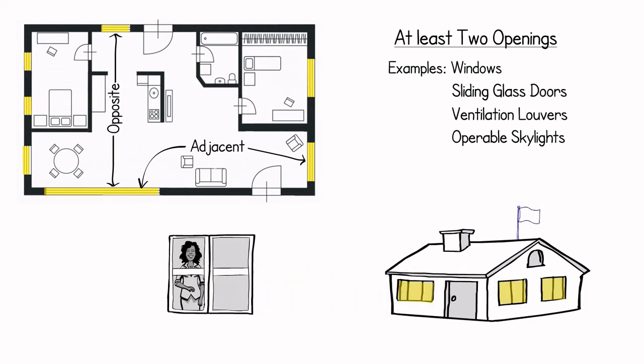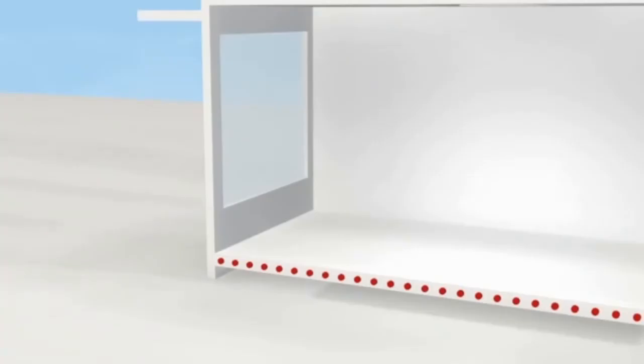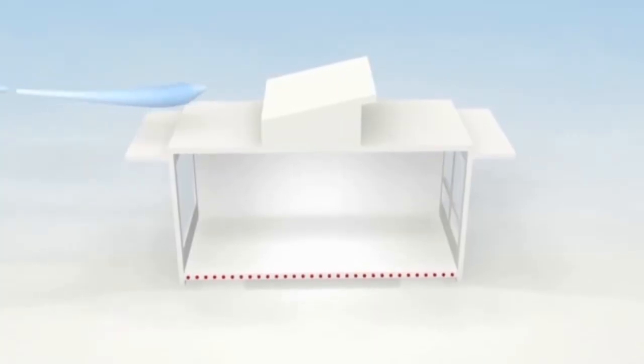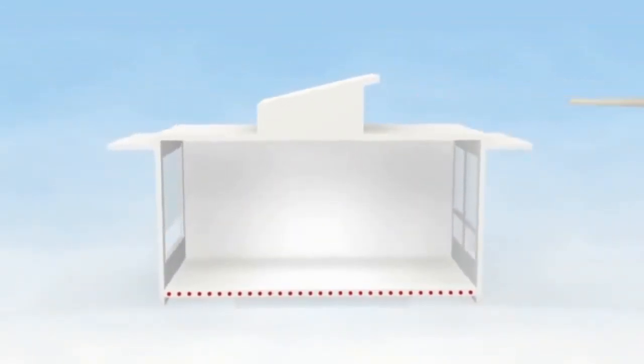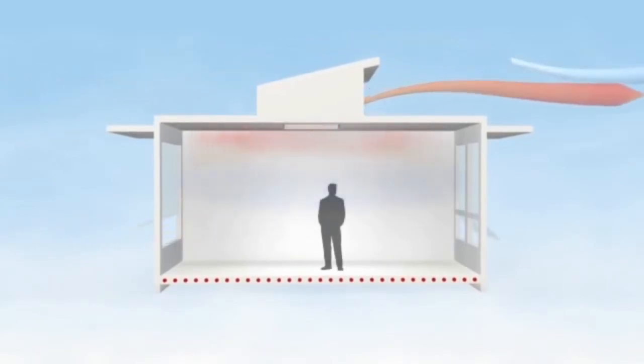The amount of heat to detach from a building, house, or infrastructure is directly affected by those areas. If the inlet and outlet areas are bigger, then more air can travel through, meaning more heat can be removed, and vice versa. However, discomfort will be created if inequality is observed — meaning the air coming in is higher than what is going out or vice versa. An equal amount of airflow volume going into a building as exiting the building is the ideal outcome.